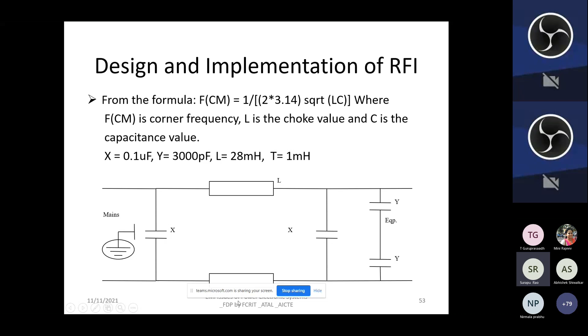Okay, so after this filter was implemented in the power supply section, you connect line, neutral and ground here, and then ahead of this will be your equipment. So we have implemented the power supply filter, the RFI filter, that will take care of whatever conducted emission we have seen. After this, again we have taken the reading. Now see, you can see that almost everywhere the readings are now coming below the specified value of the standard for conducted emission.